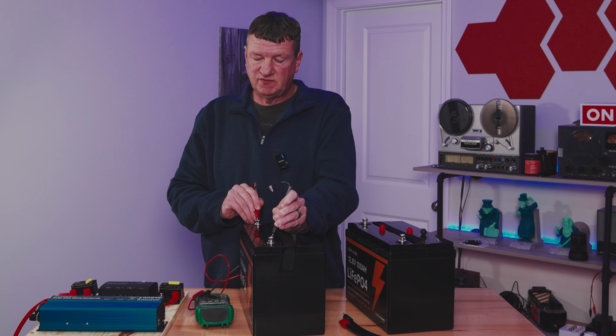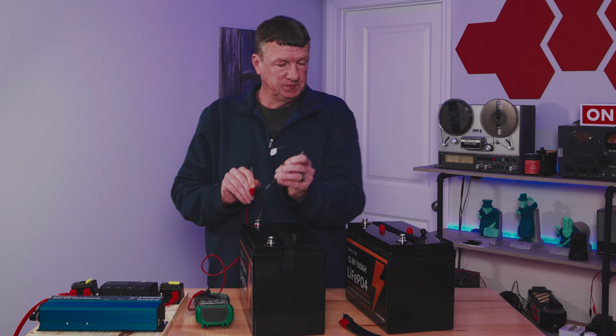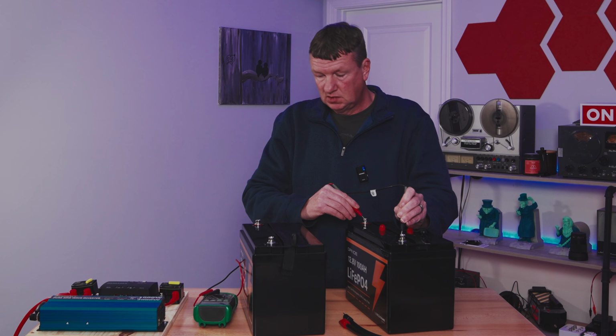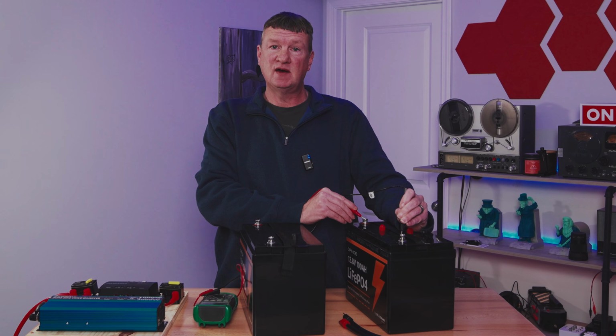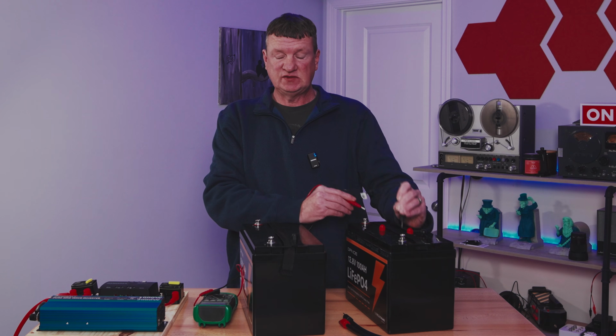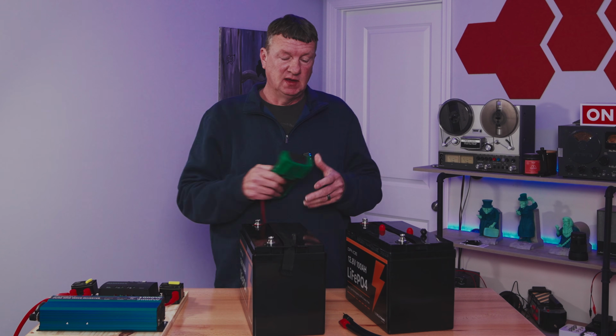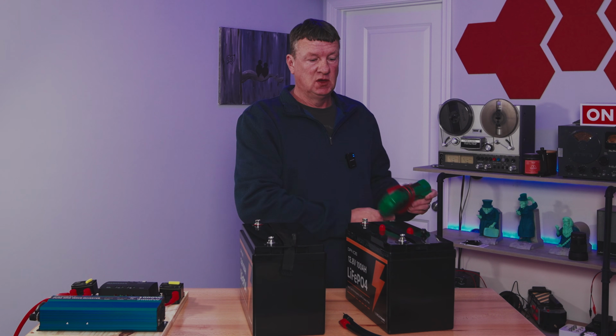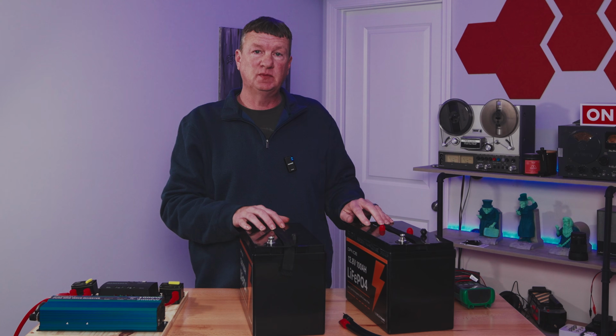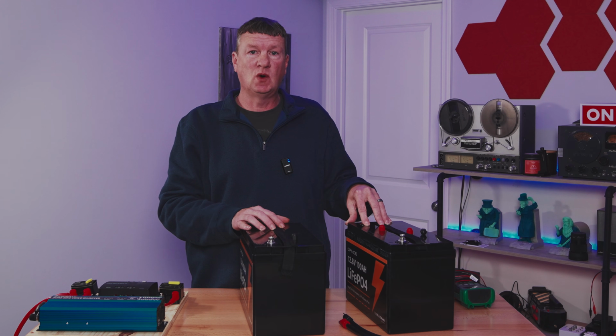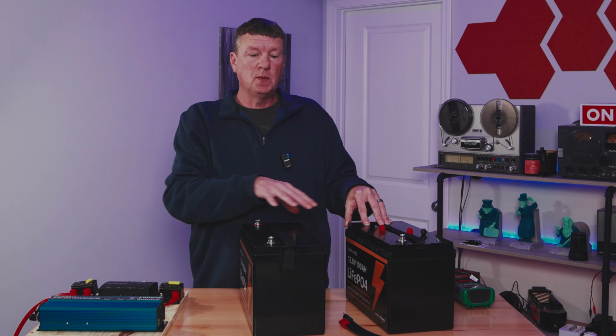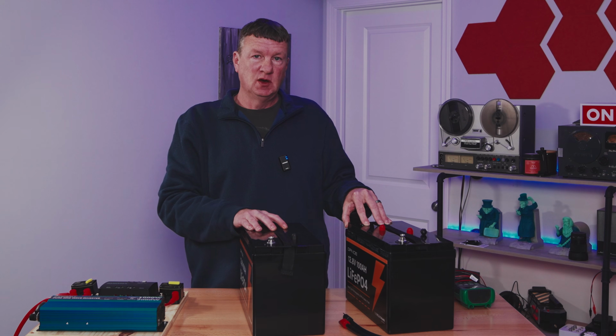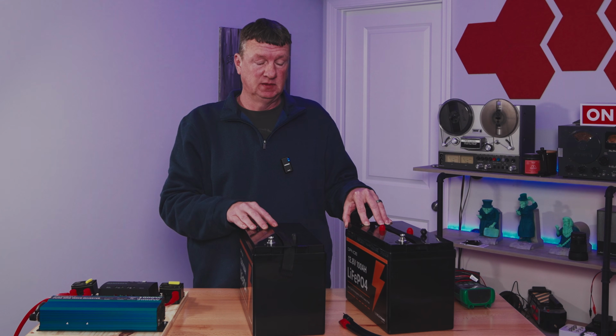On my first battery, I have 13.24 volts. On the second battery, I have 13.42. That's not too bad, I wouldn't worry about that. But if it was off any more than that, you would want to connect the batteries using a 2 ohm, 10 watt resistor. This will help balance the power between the two before you connect them permanently.